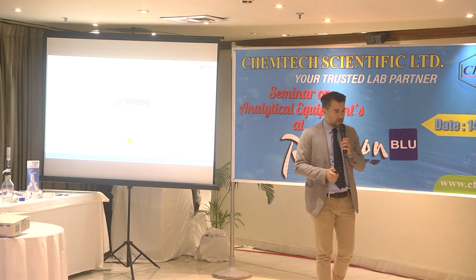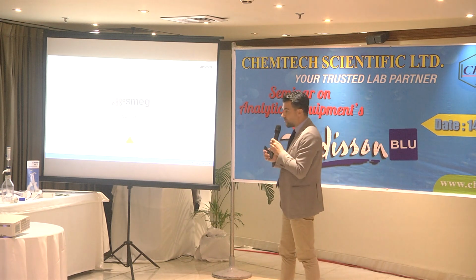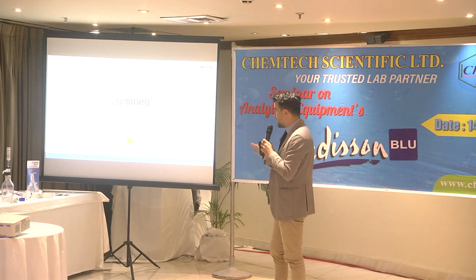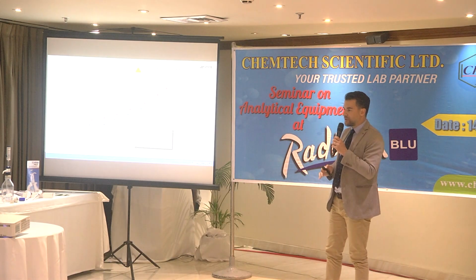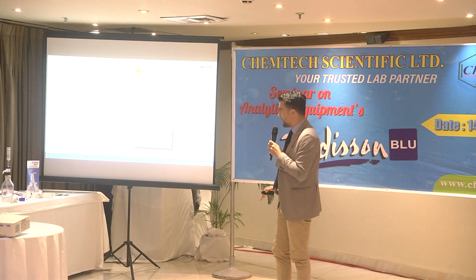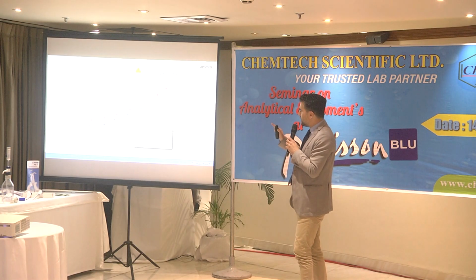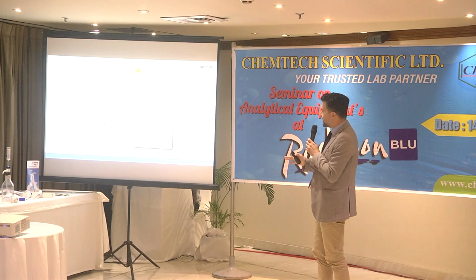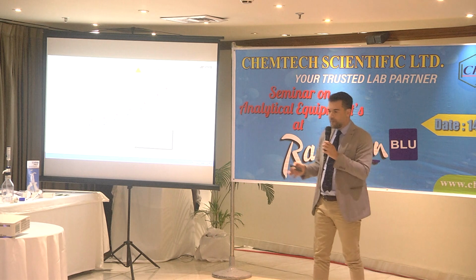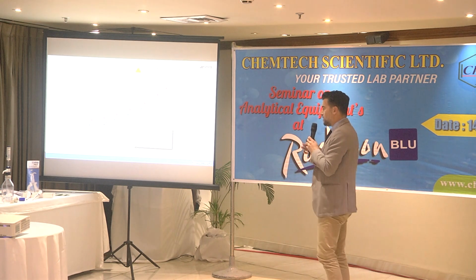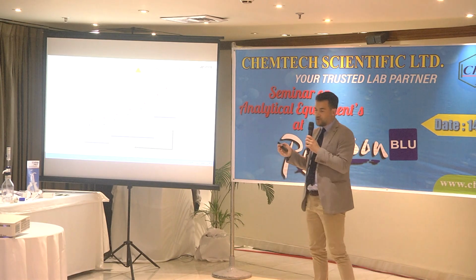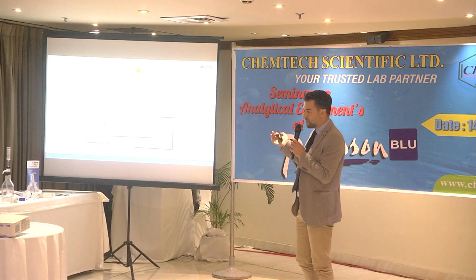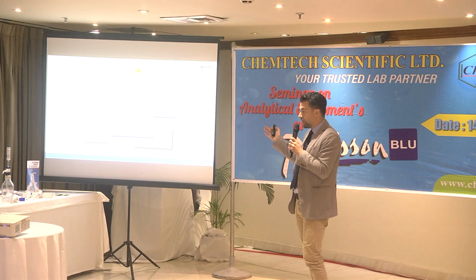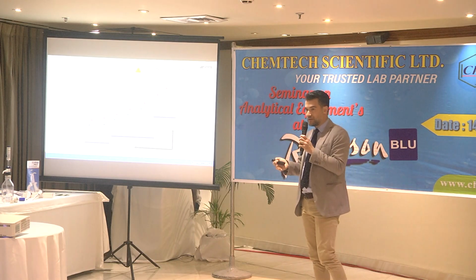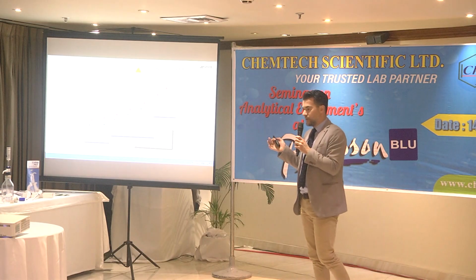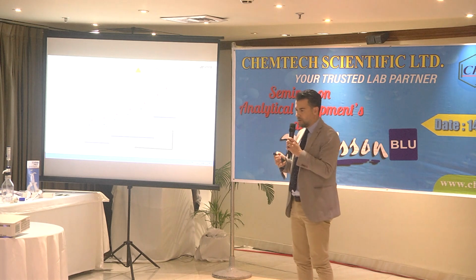Okay. We can see our product range. GW means glassware washer. All our models have this code, GW. This is the under-counter range. Under-counter means that you can place the machine under the desk, under the bench, and we have machines of increasing performance, starting from the 0 to 60, which is the basic, standard model, up to the 4090, which is the professional machine that is generally used in pharma labs. This is the most important machine for pharma labs because it's the only one that can be upgraded with a conductivity sensor. You need a conductivity sensor for your validation. Sometimes it's requested by the validation system. And only on this machine is it possible to have the conductivity sensor as an accessory.